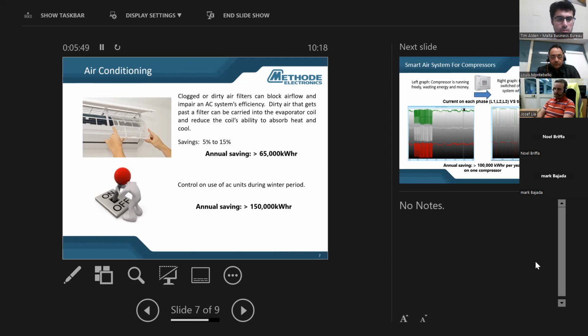Basically, we calculate that we have more than 350 units installed in our company. One of the improvements we made was to employ 2 persons to take care of cleaning the filters and the AC units. By keeping the AC systems, the indoor and outdoor units, clean, we calculate that we see a saving between 5 to 15%. It's difficult to calculate exactly.